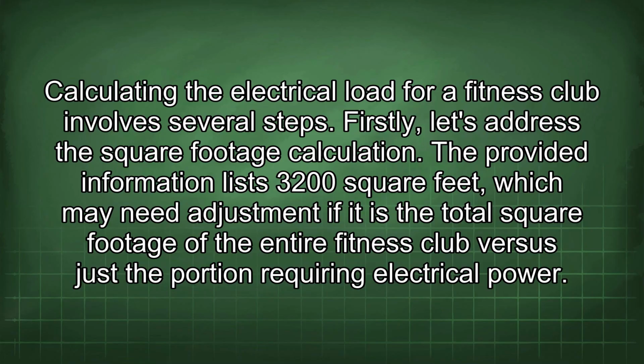Calculating the electrical load for a fitness club involves several steps. Firstly, let's address the square footage calculation. The provided information lists 3,200 square feet, which may need adjustment if it is the total square footage of the entire fitness club versus just a portion requiring electrical power.